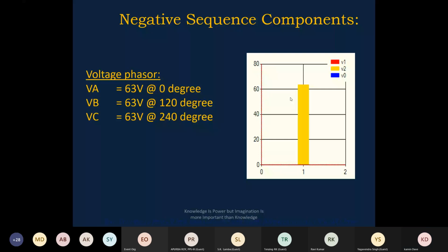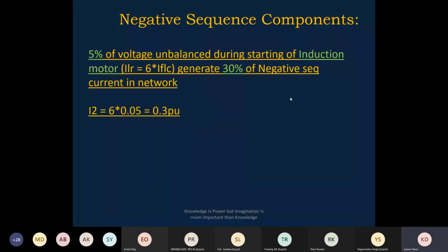So look at it here. For example, say 5% of voltage unbalance during starting of an induction motor generates 30% of negative sequence current in the network. For example, locked rotor current is 6 times the full load current. So with 5% voltage unbalance, I2 is equal to 6 into 0.05 is equal to 0.3 pu. So 5% unbalance in voltage generates 30% negative sequence current in the network.